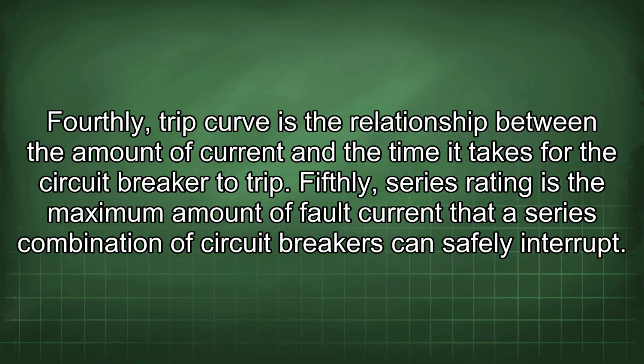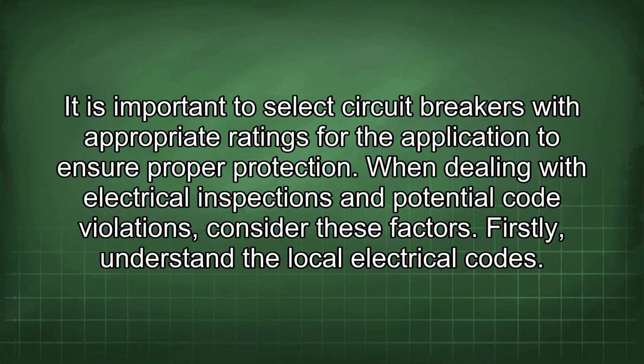Fourthly, trip curve is the relationship between the amount of current and the time it takes for the circuit breaker to trip. Fifthly, series rating is the maximum amount of fault current that a series combination of circuit breakers can safely interrupt. It is important to select circuit breakers with appropriate ratings for the application to ensure proper protection. When dealing with electrical inspections and potential code violations, consider these factors.